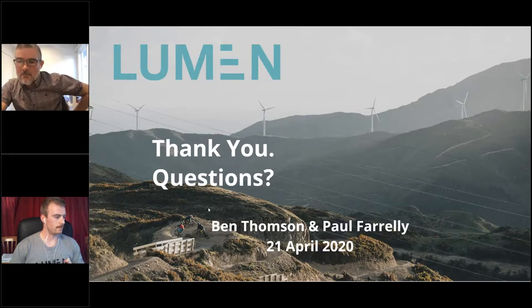Yep. Cool. Another one here. I've encountered power factor correction units that have failed, but the client has not been aware. That's not very good, is it? Suggest perhaps power factor correction is equipped with alarms. I guess so, although generally if your power factor is poor, some sort of energy management program or regular reporting would pick that up anyway using your retailer data. So we can help anyone who needs to learn how to get that data from a retailer and check it on a regular basis. That's quite straightforward. That's what I'd suggest, rather than necessarily putting in an alarm, just check your data. That's quite a common issue though with power factor correction failing. Often it can overheat as well. We've had issues where the power factor correction stopped working because it was getting too hot in the switchboard room. Absolutely.